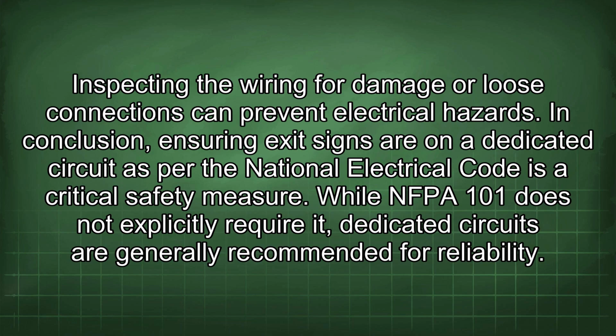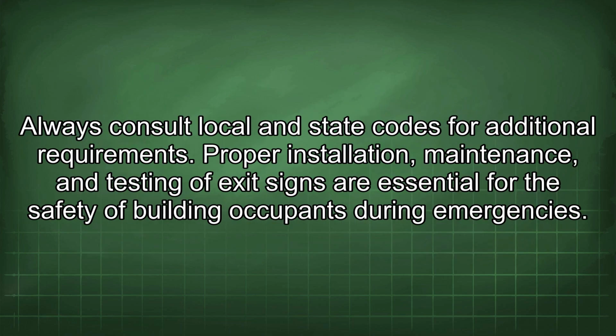In conclusion, ensuring exit signs are on a dedicated circuit as per the National Electrical Code is a critical safety measure. While NFPA 101 does not explicitly require it, dedicated circuits are generally recommended for reliability. Always consult local and state codes for additional requirements. Proper installation, maintenance, and testing of exit signs are essential for the safety of building occupants during emergencies.